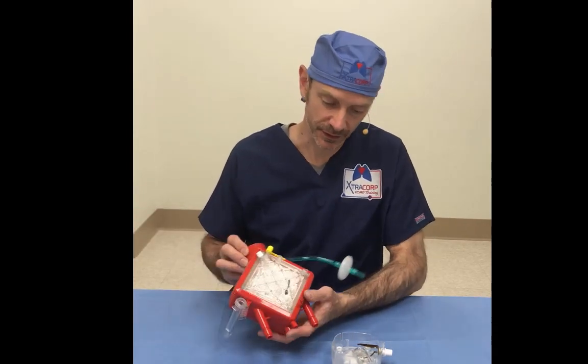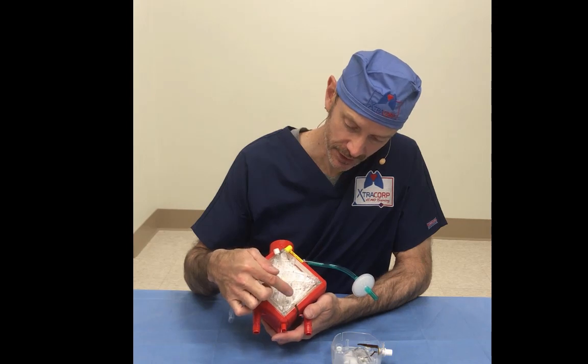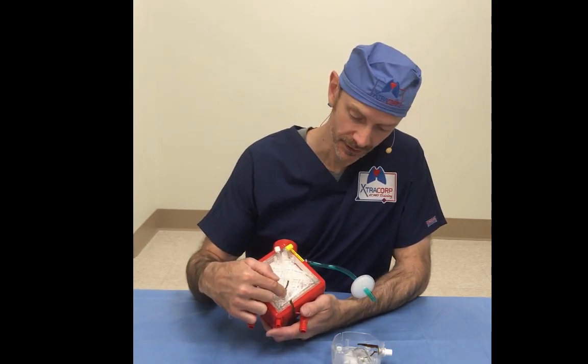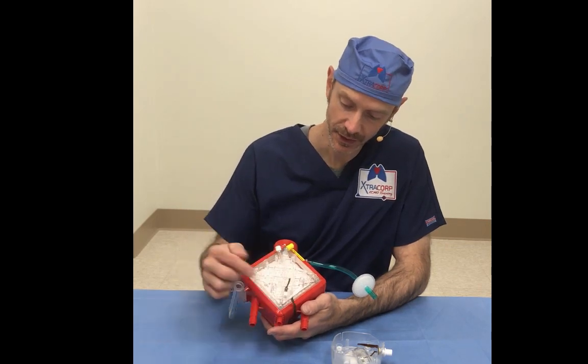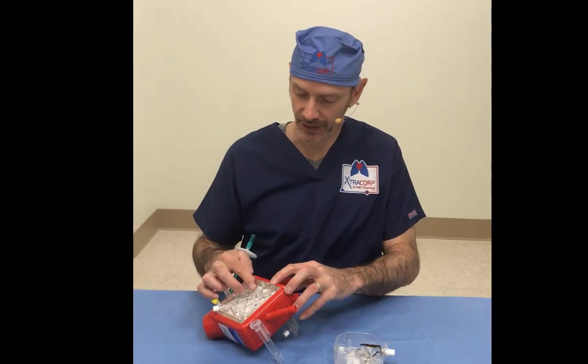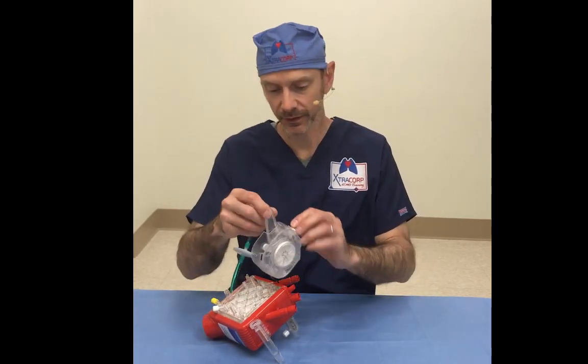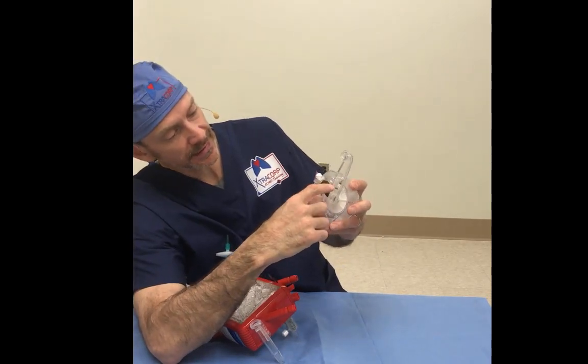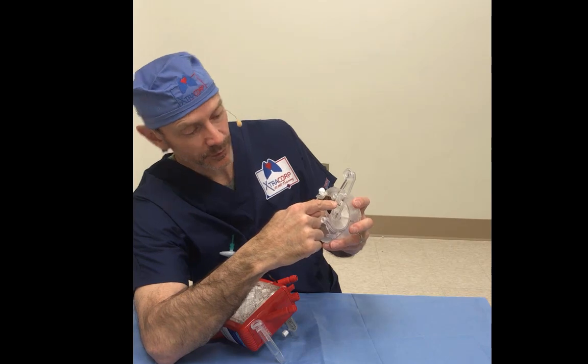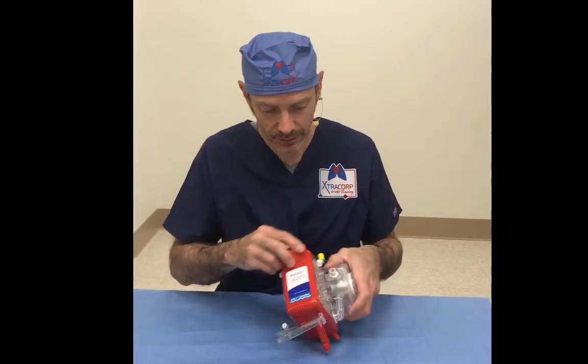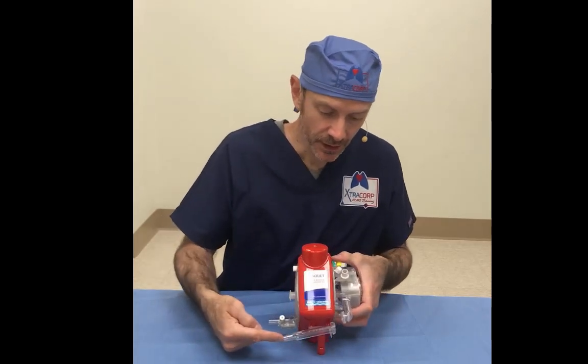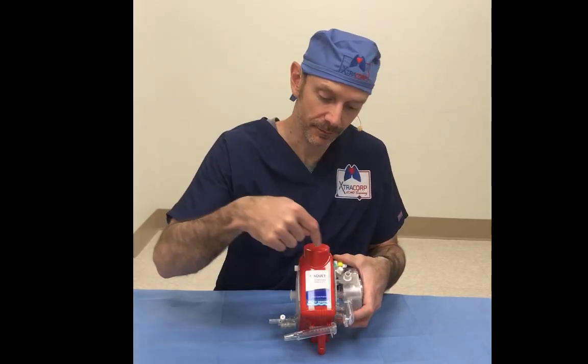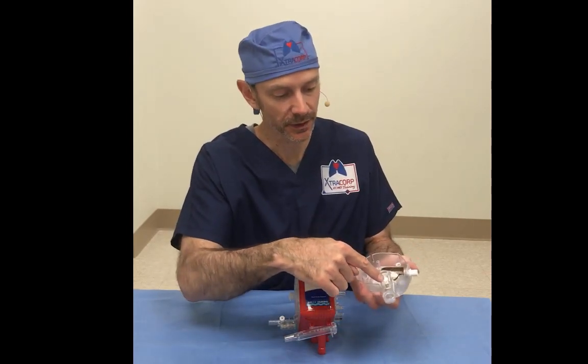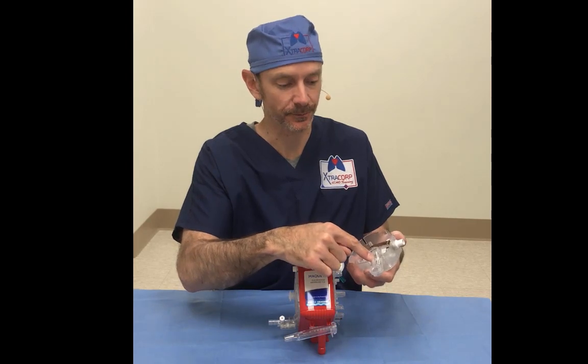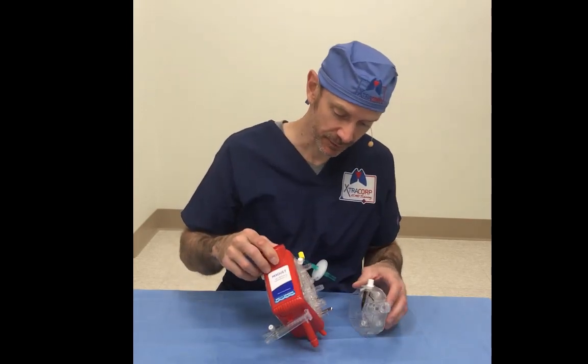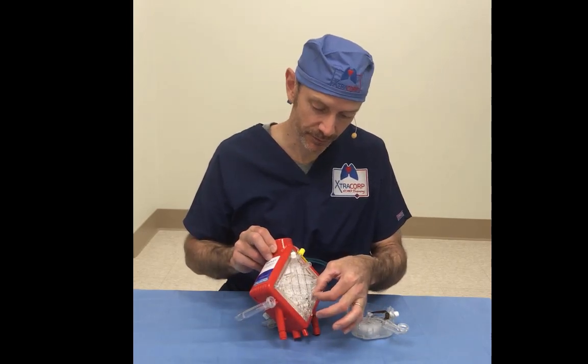Also, what we see in here is some of the electronics. So this is a pressure sensor that is attached directly to the plastic, and that has had an electronic cable that connected over here. And we have another pressure sensor on the inside, on the inlet of the pump, so we can get a venous line pressure. This would be your venous line connected to this. And the venous line pressure pre-pump is monitored right there on the inlet of the centrifugal pump. Then it goes around, comes out the other side, and now there's a pressure on the oxygenator. Here's the first pre-membrane pressure.